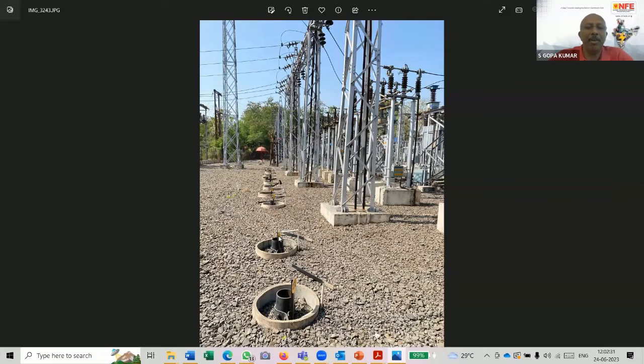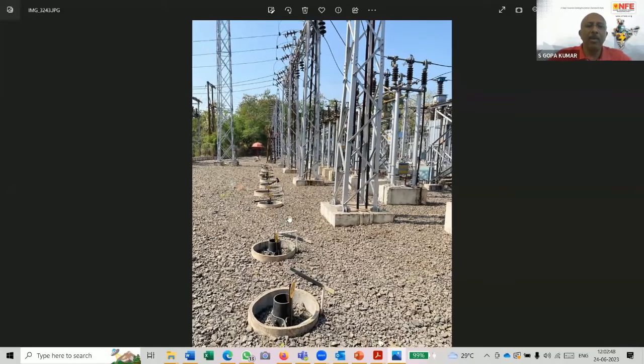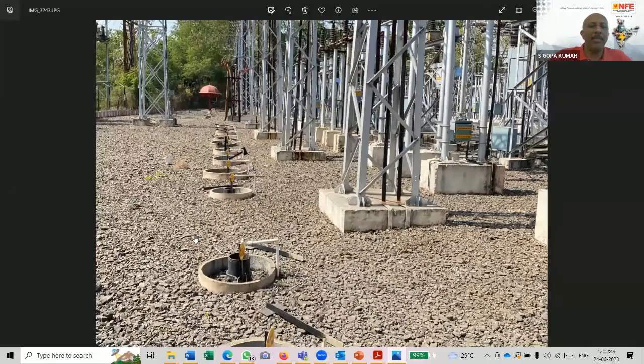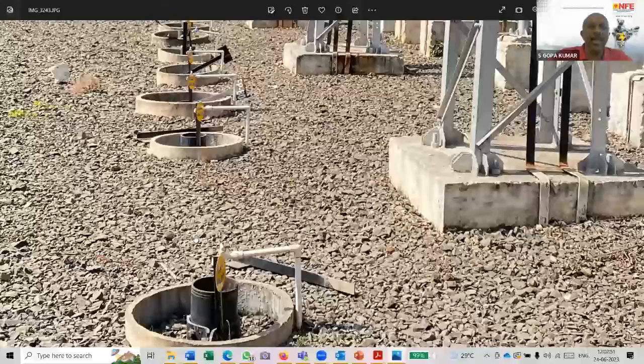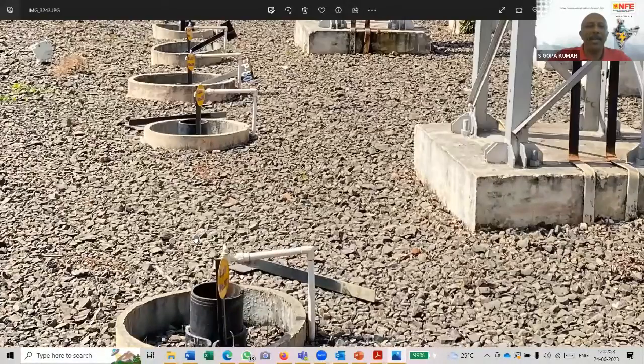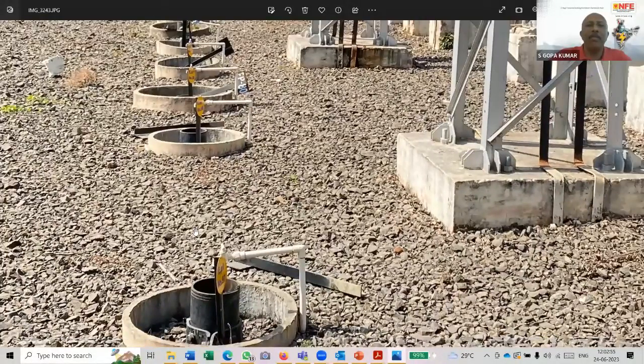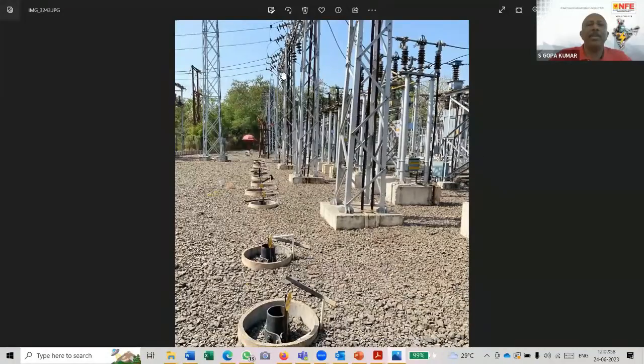This is a substation, and these wells with the pipe, is this picture visible to you on the screen? Yes. These are big cast iron earth electrodes. I think each of them is probably 7-8 meters, and there is a water pipe as well to put water every day. Each of these earth pits is connected to the outgoing 11 kV feeder of the substation, and especially to the surge arrestor.